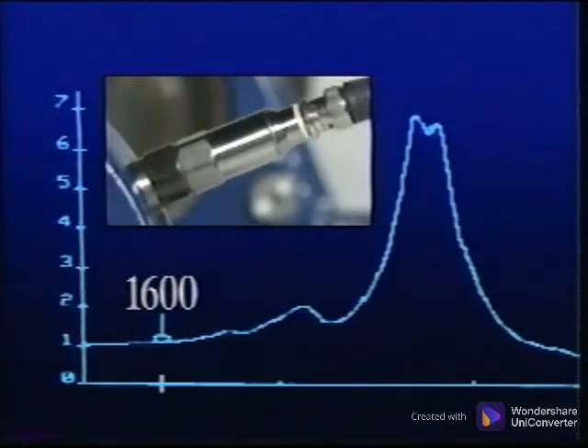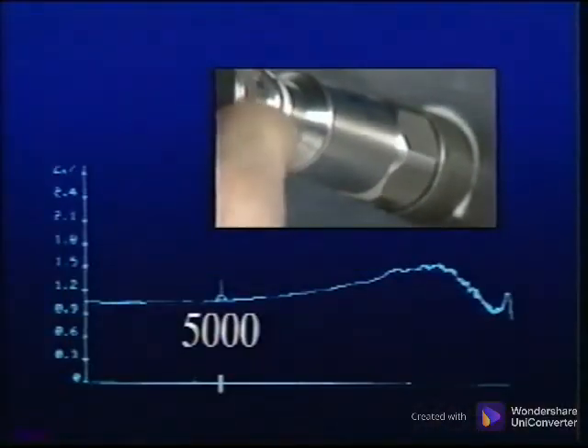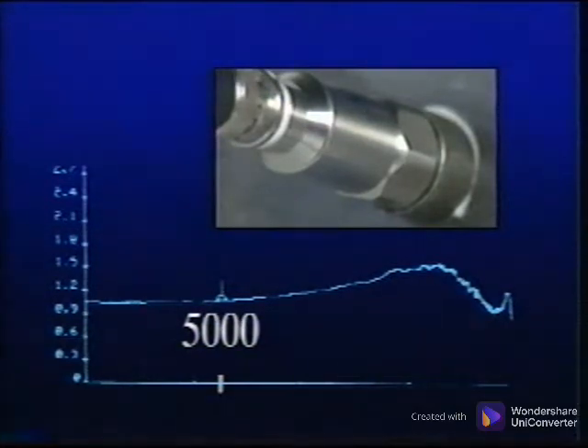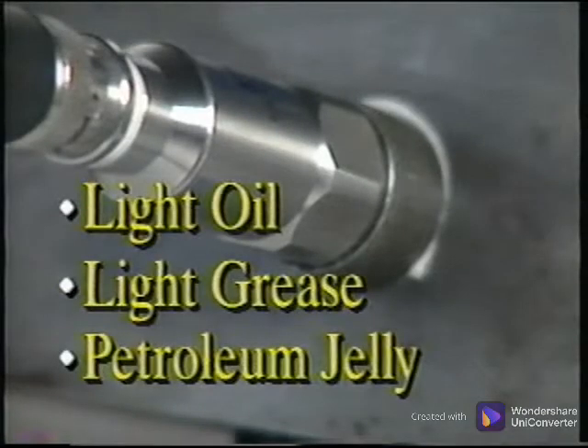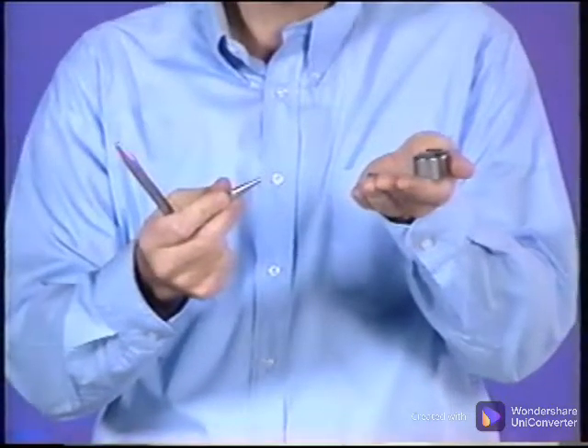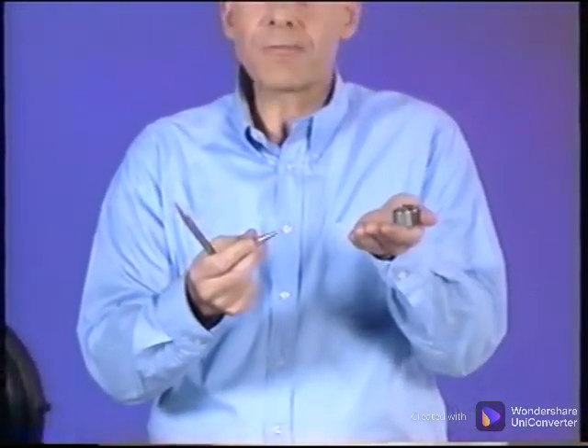There are instances when even this frequency range is not high enough. When a couplant fluid is used between the sensor and the magnet and machine, the linear response range is increased in this accelerometer to 5,000 Hz with less than a 10% variance. Typical couplant fluids can be a light oil or grease or even petroleum jelly. All of these magnets provide a greater frequency response range than either the 8-inch stinger or the 2-inch stinger.